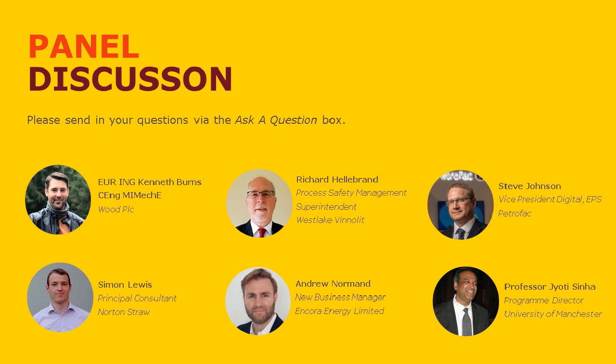I'd just add as well, in the chemical industry, the pulsation dampers are usually specified for things like piston type pumps, but they're usually based around little elastomeric bags inside pressure vessels with nitrogen. The problem with those is they're often attacked by the chemicals, but nowadays there are alternative solutions for pulsation dampers. There's no point fitting one if it's going to leak internally within an hour or two, because it's really doing nothing. You need to get the material spec right and pick the right source of pulsation dampers.